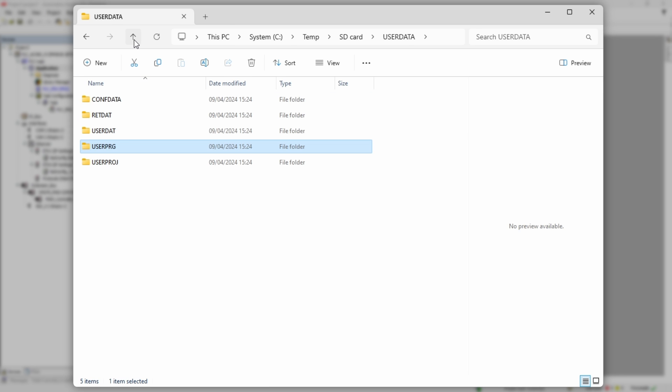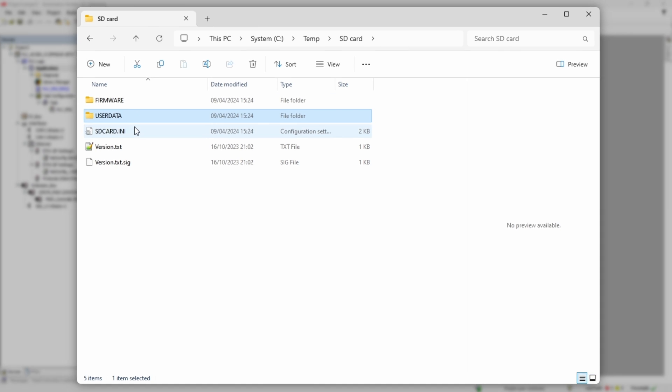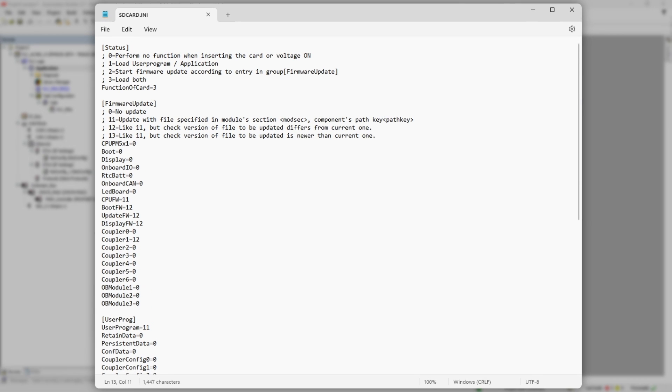Folder user data contains compiled user application with checksum CRC file. And finally, SD card INI file gives instruction to a PLC what to do during the update process. The whole file is divided in sections. Each of it starts with a keyword in square brackets. Comment lines start with semicolon symbol.